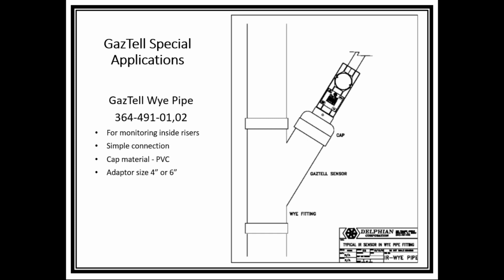So if you're interested and you've got specific needs that won't allow PVC, we can do it with other methods. But this is the most popular method throughout the country, which is basically taking a Y pipe, putting it in your 4 or 6 inch riser, and then allowing the GazTell to monitor the gas inside the pipe. Now, most of the time, you're not going to use GazTell in the % LEL range for this, because gas remediation usually has high concentrations of methane coming up from the ground. And that could be anywhere from 5 to 25% by volume. So this is really a good application for the GazTell when it's set up for % by volume monitoring.